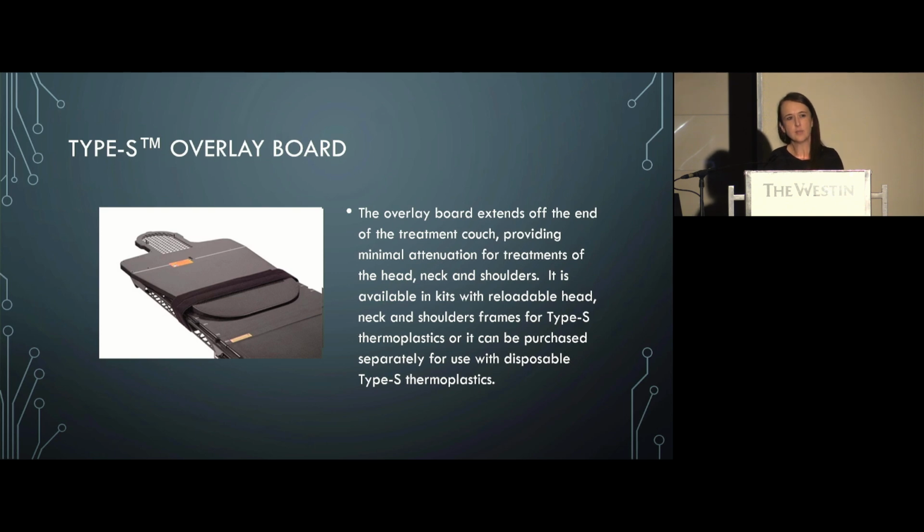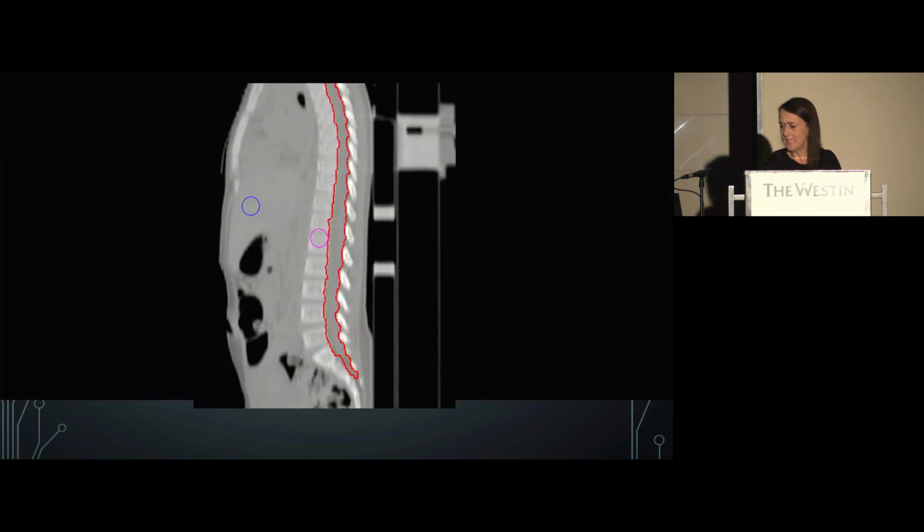Then still in terms of imaging for radiotherapy planning, immobilization equipment is imaged with the patient. So we need to ensure that the immobilization equipment can be used for radiotherapy. And why I say that is on some of our scans, specifically this was for a craniospinal patient, we noticed that there were high density inserts in the immobilization equipment in the board below the patient.